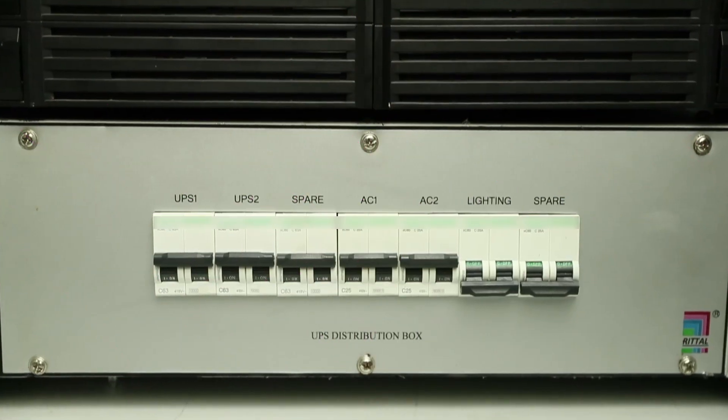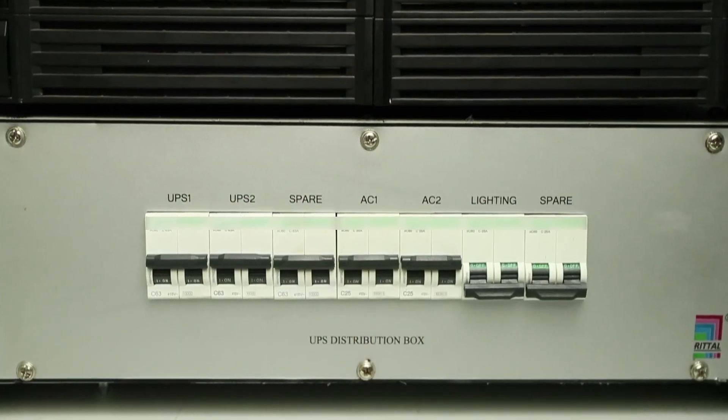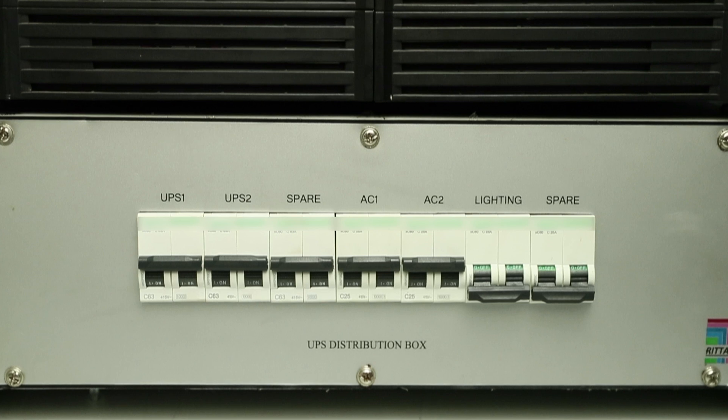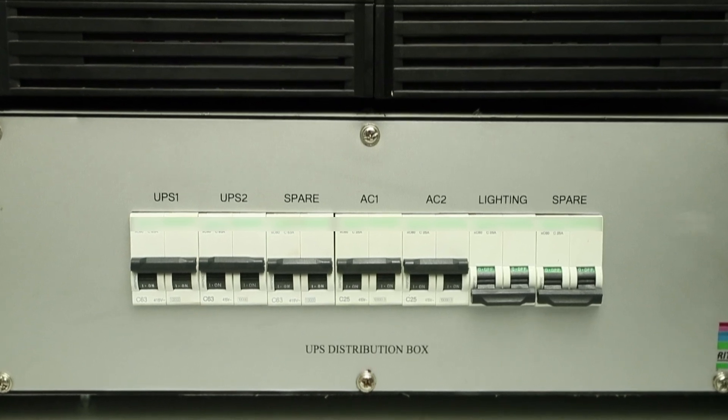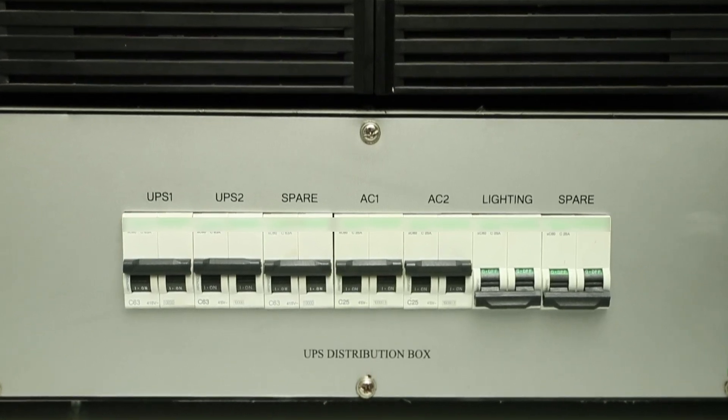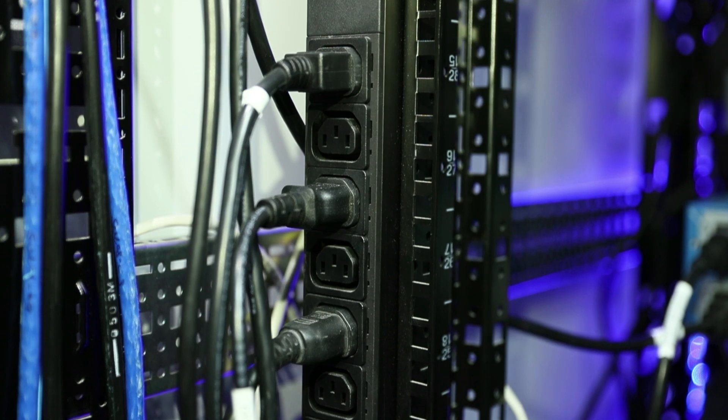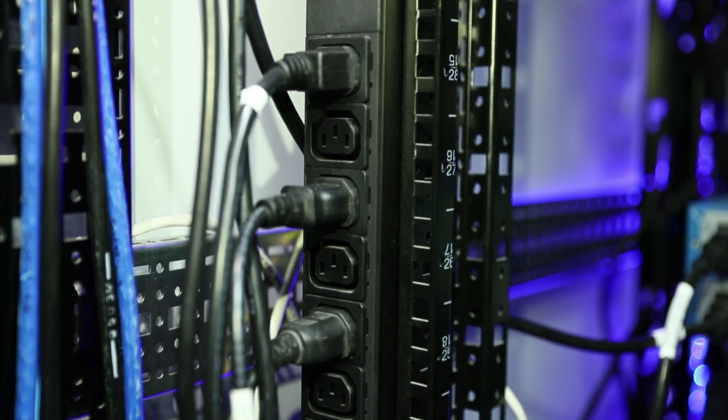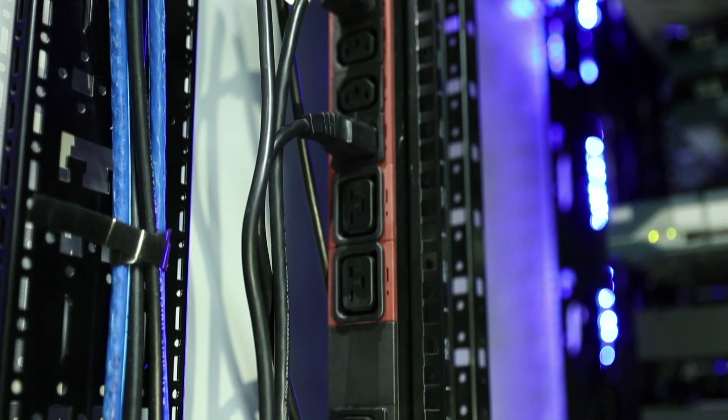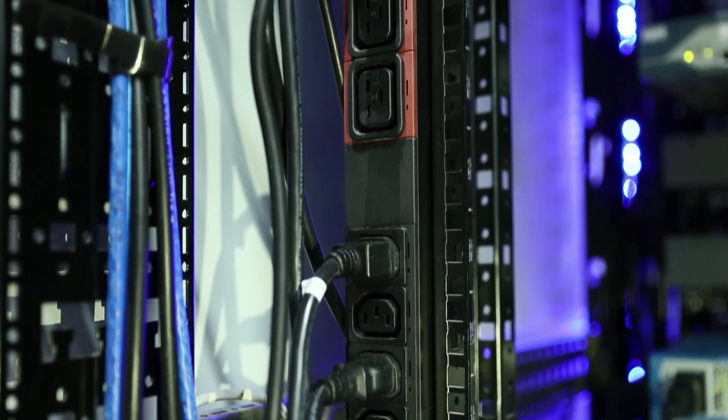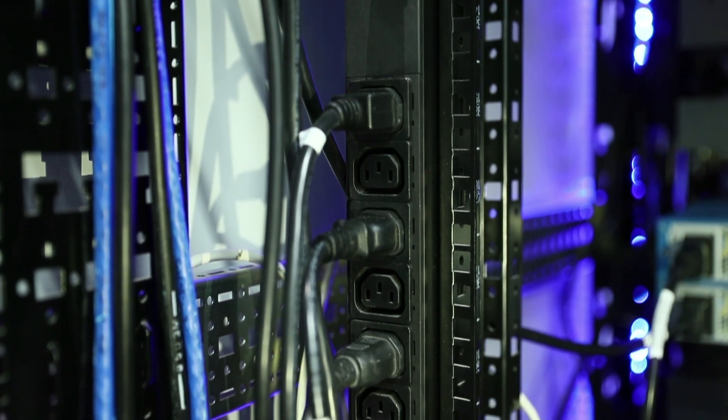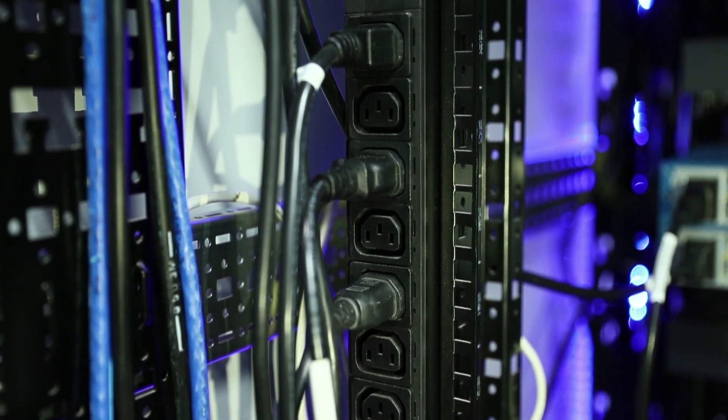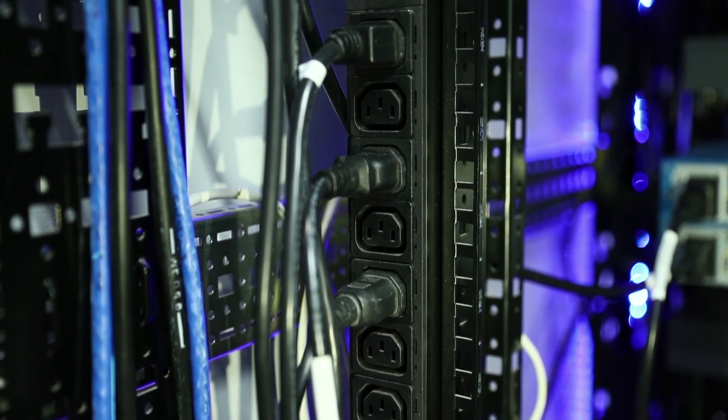This Edge data center has true online double conversion UPS in N-plus-N configuration, with power backup time up to 15 minutes. Every modular Edge data center has two power distribution units with N-plus-N redundancy, having options of metered, switched, and managed PDU, with remote management over IP.